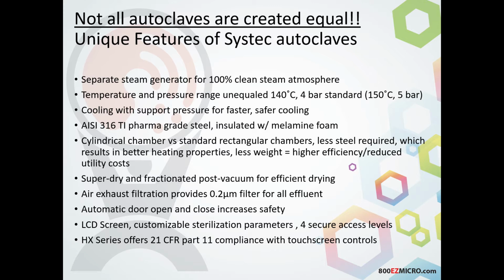We have LCD screens for them with customizable sterilization parameters and different access levels. For the HX series, where we have touchscreen controls, then we have completely programmable usernames and passcodes that can be very unique. So with the keypad systems, we don't offer as much in the way of being able to securely access that autoclave. But with all of the HX units, we have full 21 CFR compliance with the ability to program in different users, even isolate different user groups from other groups in case you have a shared autoclave. So all of that is capable as standard on the HX instrument.